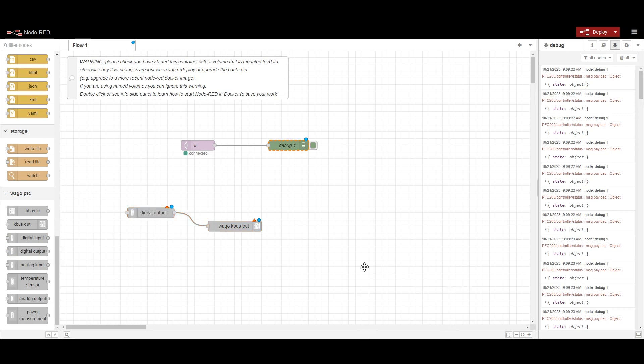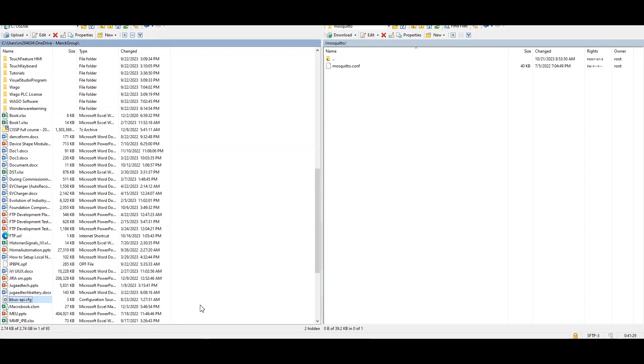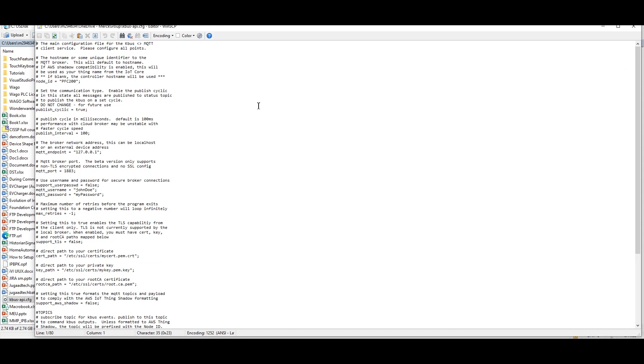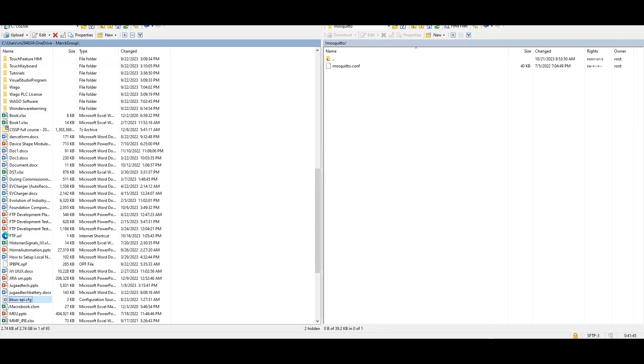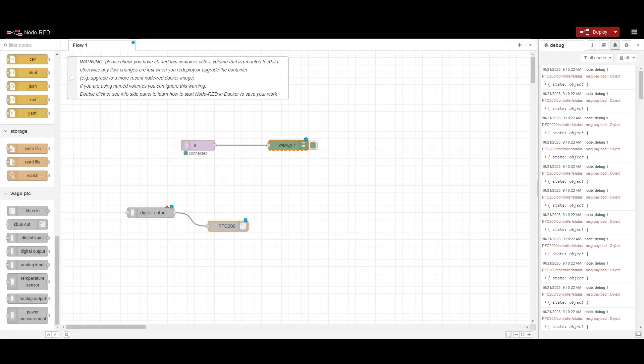We have the 'kbus in' node for inputs and the 'kbus out' node for outputs. Since I am selecting a digital output, I will use kbus out and configure the digital output card in Node-RED. In the kbus out node configuration, we set the node ID as 'pfc200' — this matches what is set in the kbus API configuration file. It is very important that the node ID is the same in both places. Once configured and we click done, this configuration is complete.